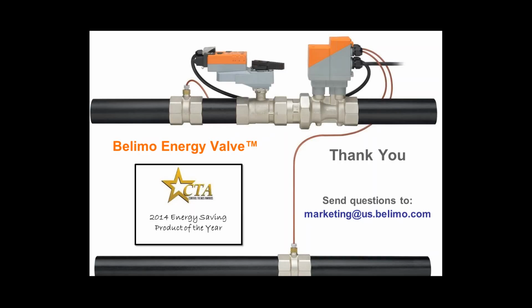Once we do that, the pumping will go down, your chiller will be seeing less water and higher delta T. So as we slow that water down, the return water's warmer, and so it hits your chiller warmer, and so you're getting a higher delta T as you bring it down. So what you're looking at there is a fairly typical scenario where energy valve can come in and start to correct the vast majority of what's going on there. And again, it depends upon how your building or campus is set up, but we'd be happy to explore that with you if you'd like. So let us know.